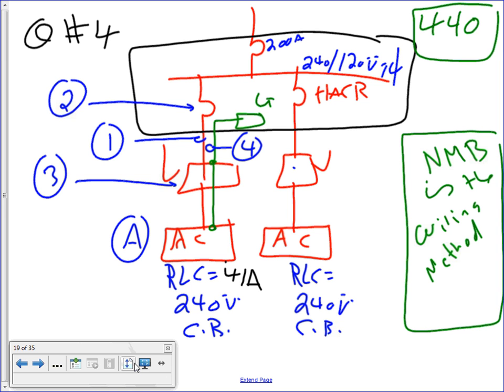Okay, I do have a couple of things for my AC unit. Same example, guys. I have an AC unit, air conditioning, rated load amps or load current 41. Let's make this one, if you guys want to exercise for it, let's make it 55, will ya? Rated amps of 55 for that boy. I'm going to only do A. You guys will do B as an exercise if you decide to practice. Rated load current on the nameplate given as 41 amps. 240 circuit breakers we're using.